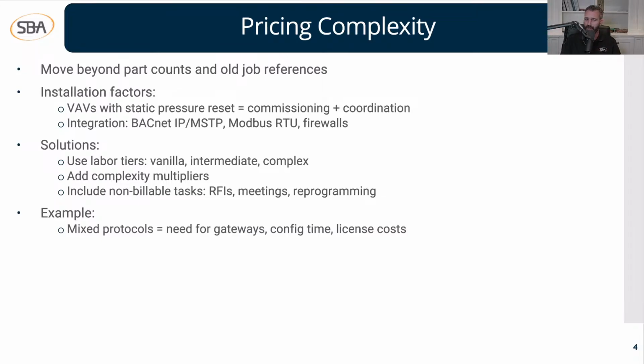Also, whenever you see that a system is BACnet over IP to the supervisory, but MSTP at the field, and they want to integrate a Modbus boiler controller, don't just think it's the same protocol. We need to make sure we're aware that we might have to switch protocols if it's a different type of protocol in the boiler control panel.